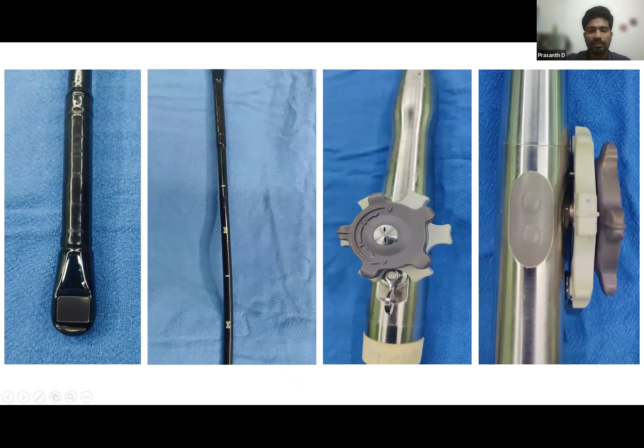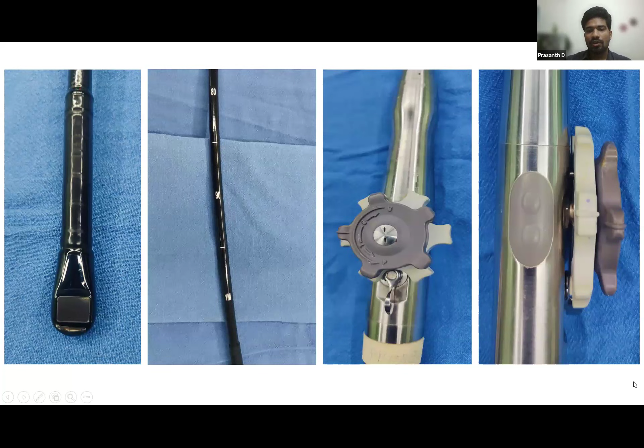As we can see here, the first image is focused on the distal tip or lens of the transesophageal probe, above which we can see the bending portion, which we can control with the transducer control. This is the full shaft. The second video shows the full shaft. The adult probe is about 100 centimeters in length. And in the third image, we are seeing the control housing with the larger and the smaller wheels. And this is the button for change in omniplane angle from 0 to 180 degrees.